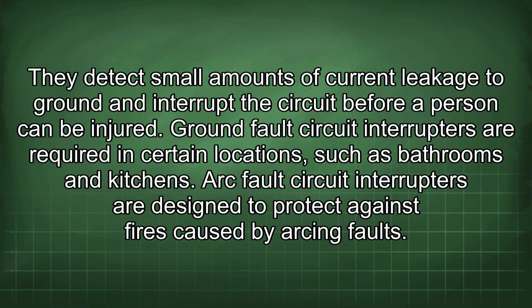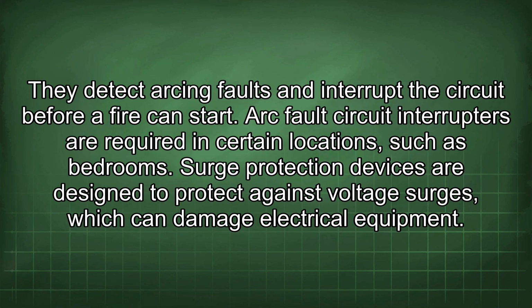Arc fault circuit interrupters are designed to protect against fires caused by arcing faults. They detect arcing faults and interrupt the circuit before a fire can start. Arc fault circuit interrupters are required in certain locations, such as bedrooms.